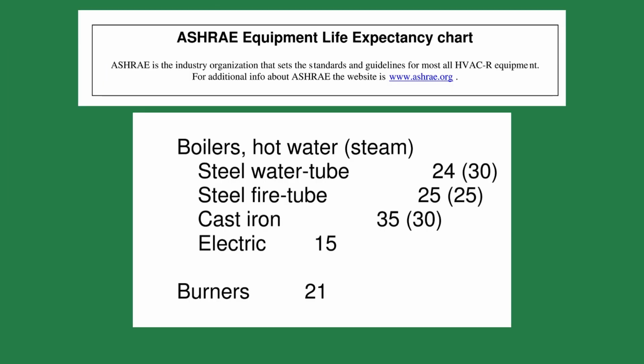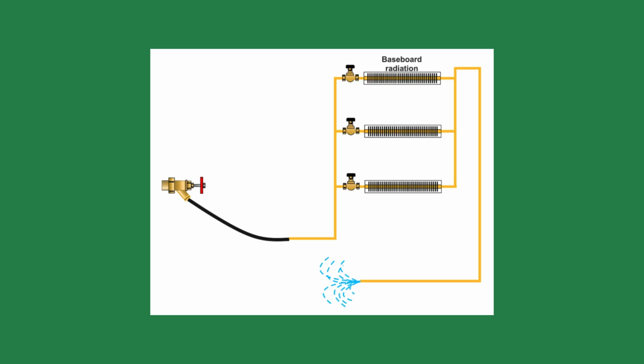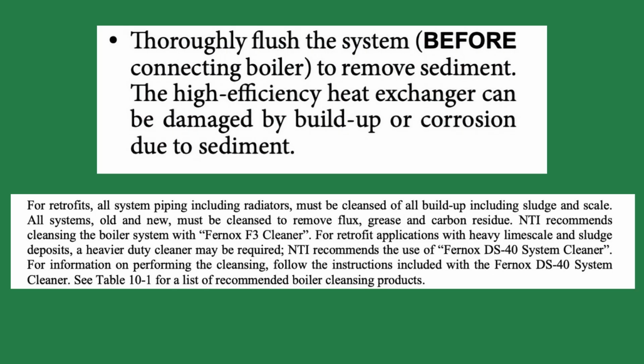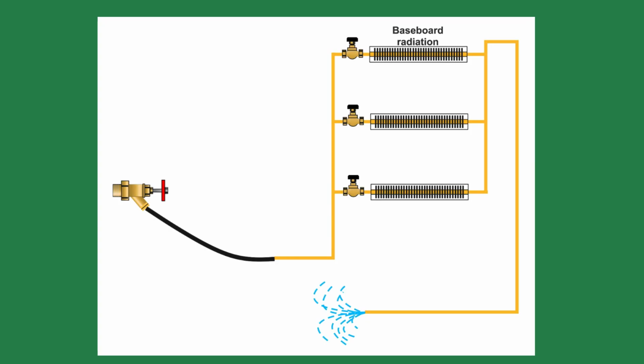Installing a new boiler in a hydronic heating system is a major investment. Whether it's in a school, hospital, home, or commercial facility, the expectation is that the new boiler will run efficiently, safely, and reliably for many years. Unfortunately, one of the most overlooked steps during installation is also one of the most important: flushing the system piping before connecting the new boiler. Skipping this step can lead to serious performance issues, costly repairs, and even premature failure of the equipment. Let's explore why flushing is critical, what problems it prevents, and what can happen if it's ignored, especially when old glycol is part of the equation.